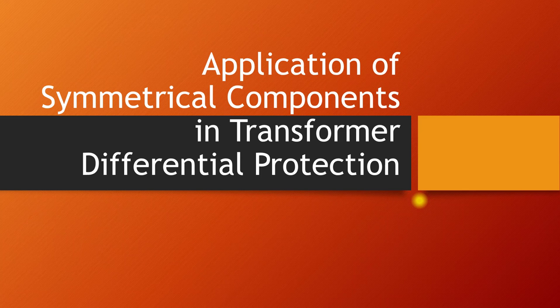Welcome friends. Today we will learn about the application of symmetrical components in transformer differential protection. The symmetrical components theory is also applicable to transformer differential protection. The transformer circuits are connected on the primary and secondary sides, and the transformer windings can be connected in delta or star configuration. Delta-star connections behave differently for symmetrical components. Let's draw a simple delta-star transformer as an example.